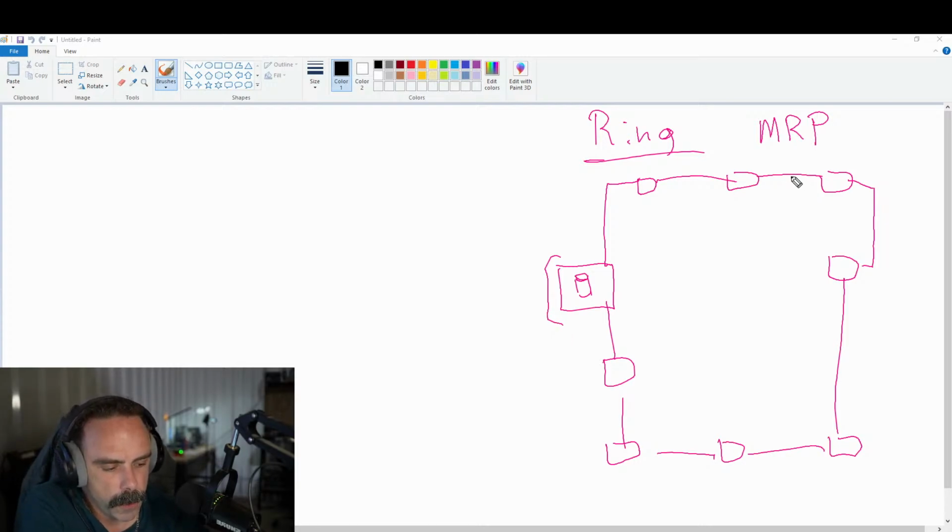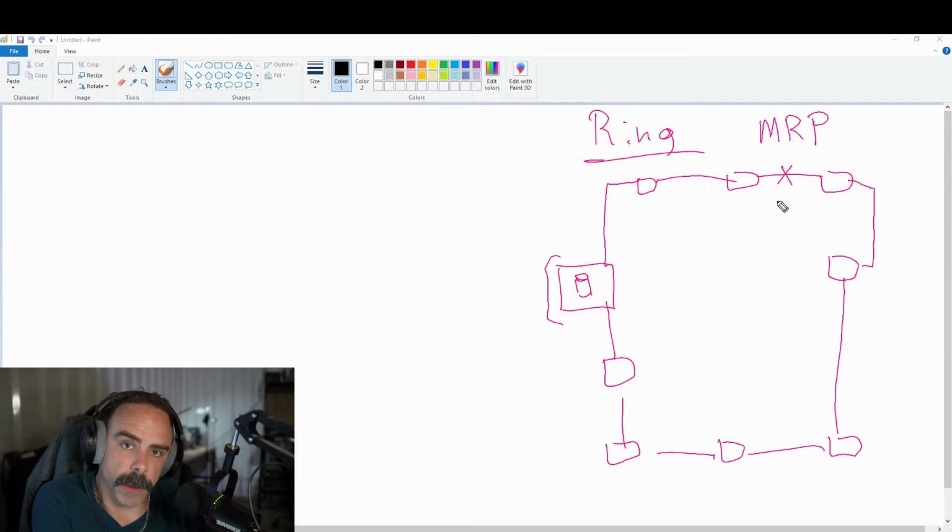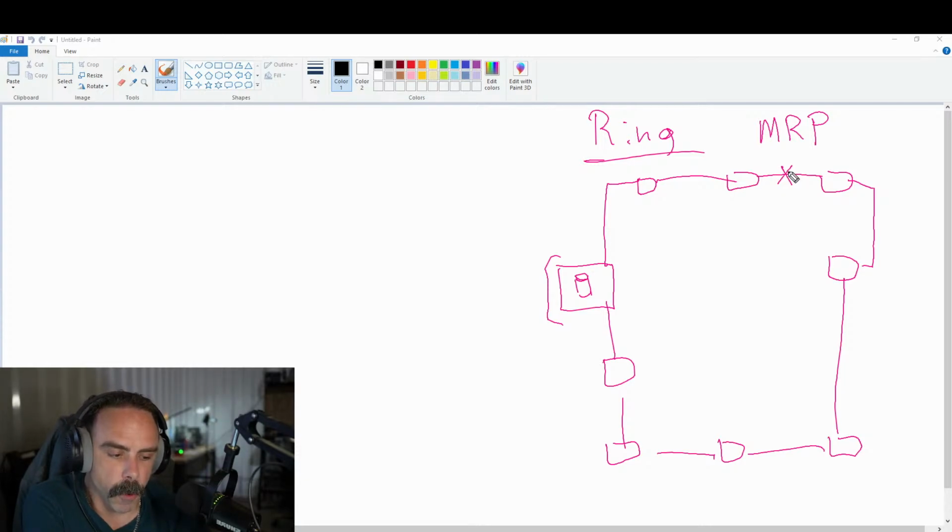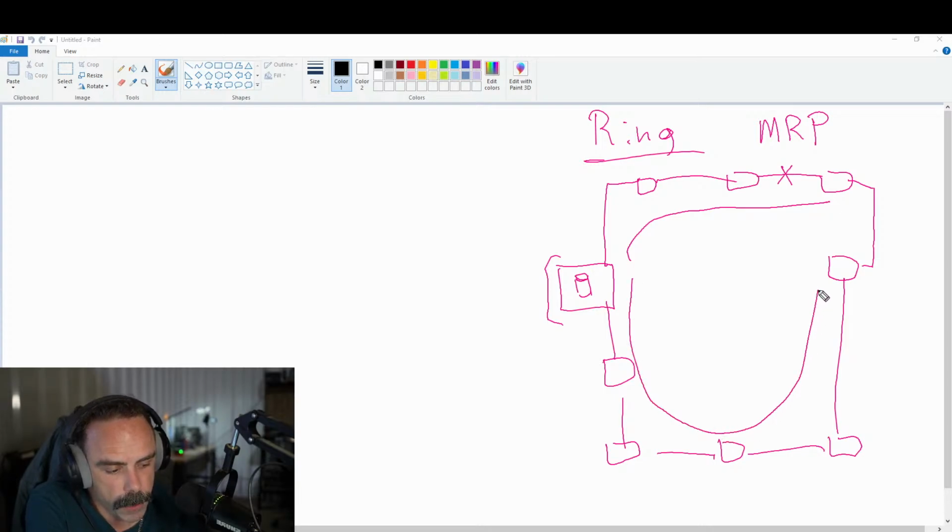Say we lose this connection. The number of devices that would actually lose communication would be 0. If something happened, if a forklift ran over that conduit and broke that cable, we would lose 0 connection to devices. Because even this here, if the route was going here, it would reroute that data very quickly back around when this was broken, and it would get to that device.